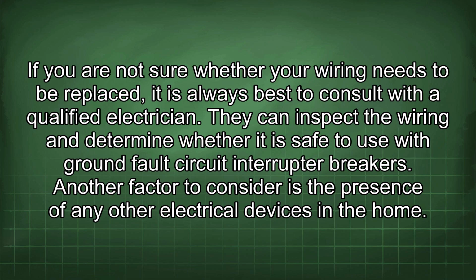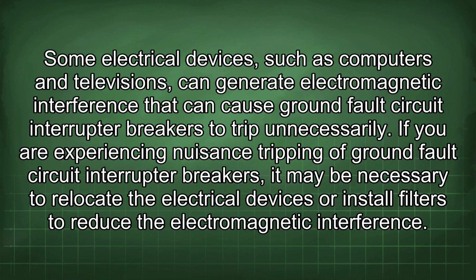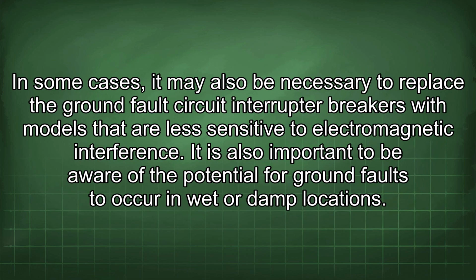Another factor to consider is the presence of any other electrical devices in the home. Some electrical devices, such as computers and televisions, can generate electromagnetic interference that can cause ground fault circuit interrupter breakers to trip unnecessarily. If you are experiencing nuisance tripping of ground fault circuit interrupter breakers, it may be necessary to relocate the electrical devices or install filters to reduce the electromagnetic interference. In some cases, it may also be necessary to replace the ground fault circuit interrupter breakers with models that are less sensitive to electromagnetic interference.